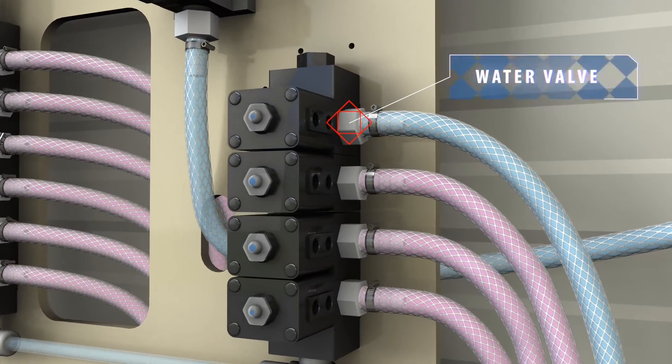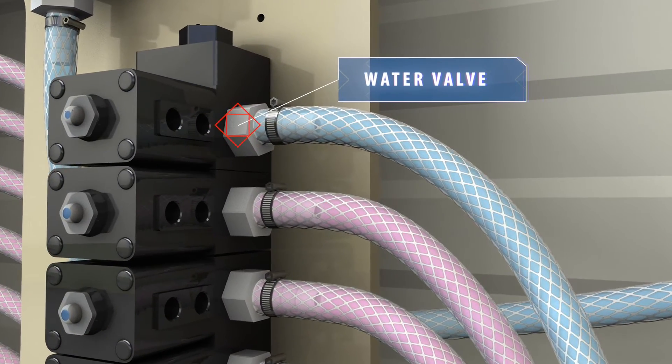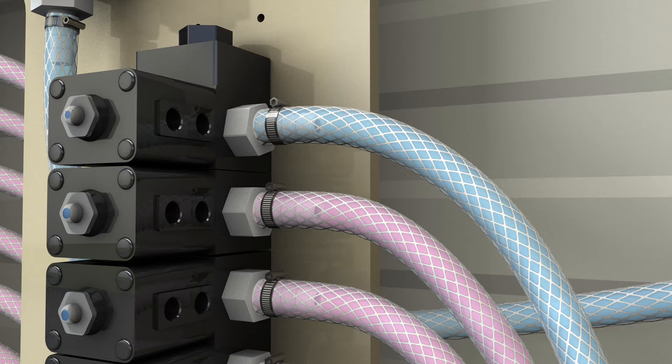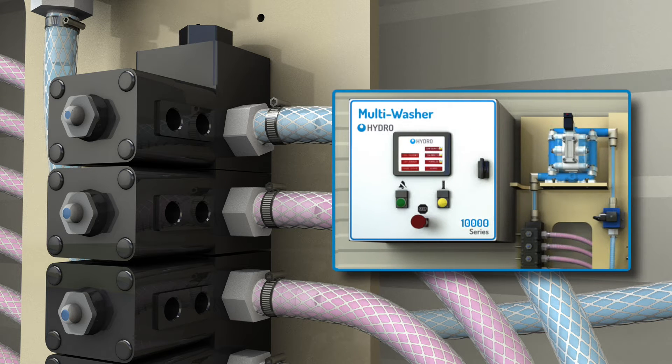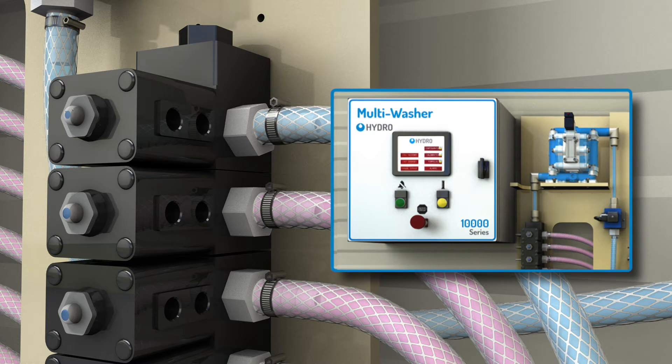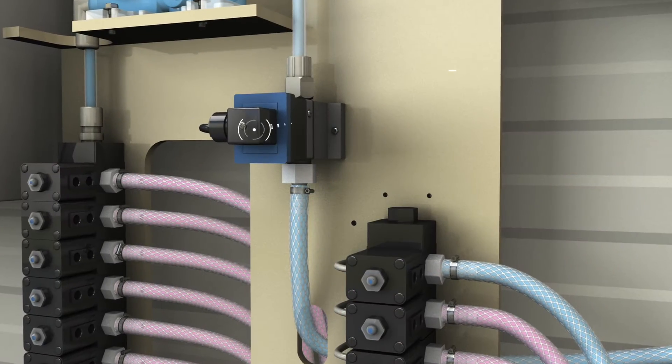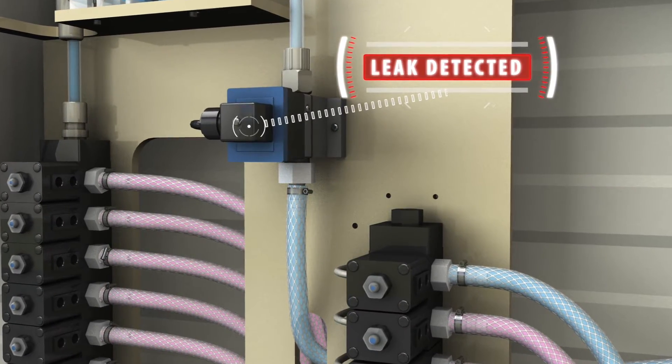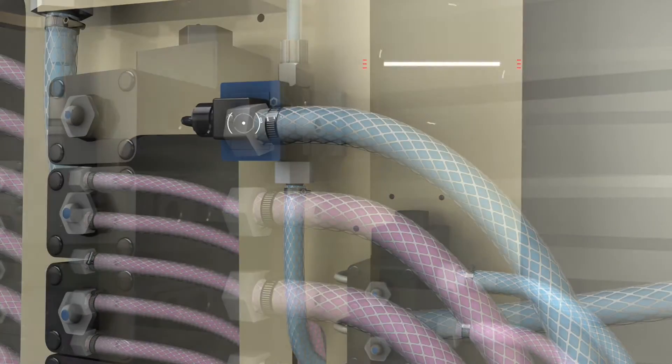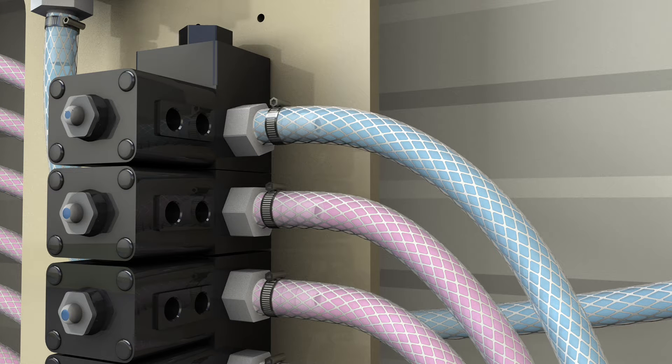During the leak test, the water valve opens at the collector which pressurizes the channel while product valves and distributor valves remain closed. If the programmable logic controller or PLC detects pulses from the flow meter, that means there's a leak and the dosing is aborted. At the end of the leak test, the water valve at the collector remains open.